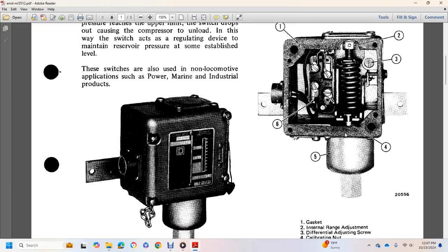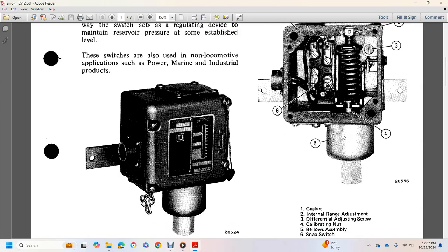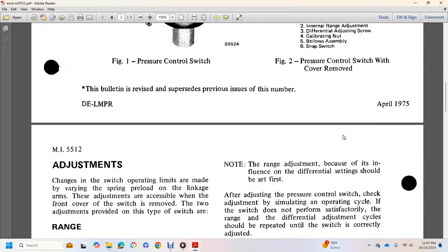Alright, 1 is a gasket, 2 is the internal range adjustment, 3 is the differential adjusting screw, 4 is the calibration nut, 5 is the bellows assembly, and 6 is the snap switch.